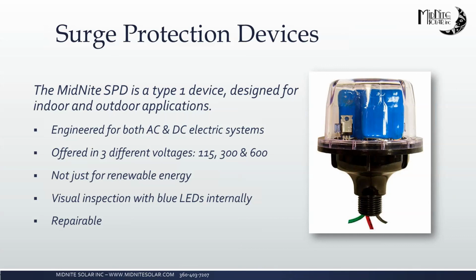So it's not just for renewable energy. You can use these for the AC coming into your house as well. We do recommend them because you can get lightning-style surges from the grid. They have a visual inspection with their blue LEDs. You'll see those light up when there is power coming through them, as long as that SPD is functioning appropriately. If it is no longer functioning due to wear or a lightning strike, those LEDs will go out, and then that unit needs to be replaced. It does have a 5-year warranty that is inclusive of it doing its job. So if you do get a lightning strike and that SPD is damaged and no longer functions due to stopping that surge, you can send it back to us within 5 years and we will replace it for free.